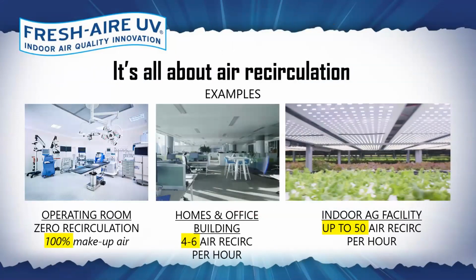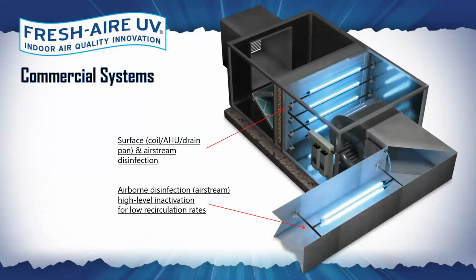Now, unlike an operating room that might be bringing in 100% makeup air with no recirculation, schools, office buildings, shopping malls, your residential home, well, they're a closed system. Typically, we're looking at between 4 and 6 air recirculation rates an hour. So, comparatively speaking to a hospital with 100% makeup air, we don't need as much UV because we have that second, third, fourth sunburn as the air recirculates through the UV system itself. So for schools and shopping malls and office buildings, we could put in a duct mount unit. There's no problem, and plenty do.